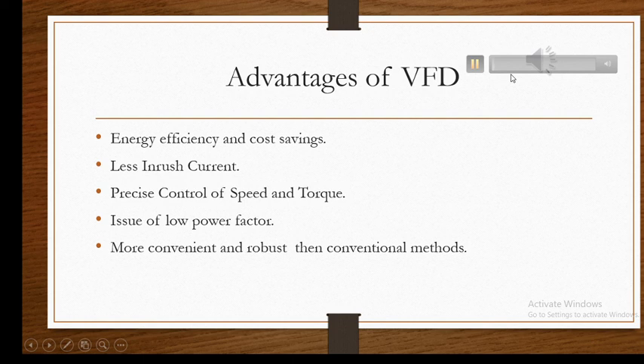The advantages of using variable frequency drives for speed control of induction motors are that they bring energy efficiency and cost savings. Less inrush current is consumed by the motor. You obtain precise control of speed and torque. The issue of low power factor at rated conditions is resolved, and it's a more convenient and robust method to control the speed of the motor as compared to the traditional methods.